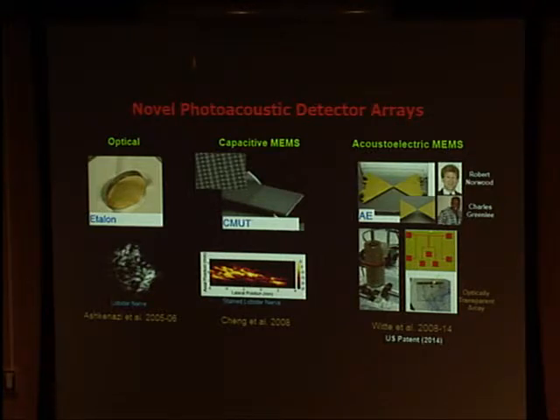Because once you get higher than 20 to 30 megahertz, it's very difficult to cut the crystal and do it in the right way. The only company that I know of that does a good job, and has some patented laser cutting technology, is Visual Sonics. We have some transducers with the mouse imaging system, which is actually a core system, but there are very few examples where you get really arrays of high-resolution piezoelectric receivers. So this probably has 100 megahertz bandwidth compared to typically 20 or 30 megahertz for piezoelectric.